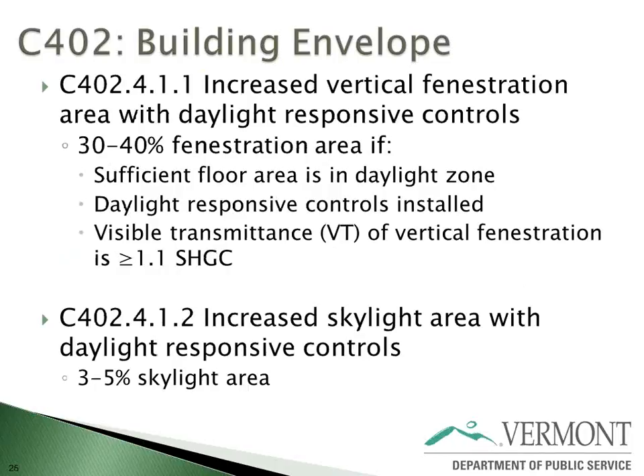So this is what that refers to. If you want to increase your vertical fenestration, in layman's terms, more windows, you can go up to 40%, back to where we were in the code before, but you have to follow a few key criteria to ensure you're harvesting daylight. It's basically saying, sure, add more windows if desirable architecturally, for comfort, visually, etc., but you need to scale back electrical lighting use through daylight responsive controls.